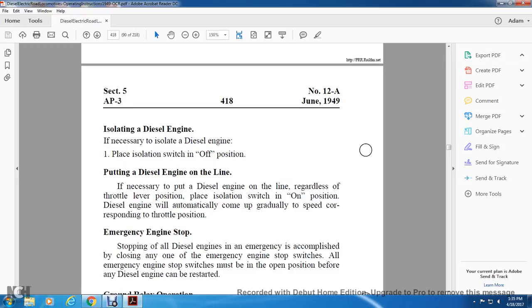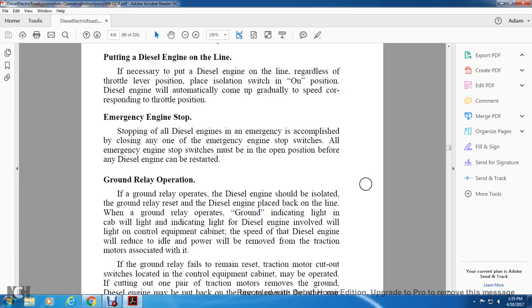Isolating the diesel engine. If necessary to isolate the diesel engine, place the isolation switch in the off position. Putting the diesel engine online: if necessary to put the diesel engine online, regardless of the throttle lever position, place the isolation switch in the on position. The diesel engine will automatically come up gradually to speed corresponding to the throttle position. Emergency engine stop. Stopping the diesel engine in emergencies is accomplished by closing any of the emergency engine stop switches. All emergency engine stop switches must be in the open position before the diesel engine can be restarted.